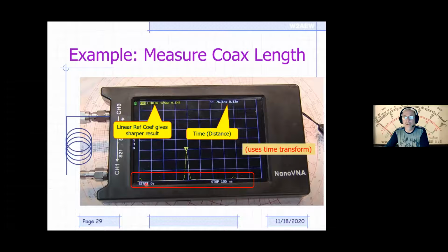So 76 nanoseconds down. Now you say, well, how far is that down my coax? It's actually the round trip delay out to the end of the coax and back. But you can tell the VNA what the velocity factor of your coax is, and it will then compute the distance for you. So in this case, it tells me that the length of that coax was 9.13 meters, or a little over 20 some odd feet of coax that I'd connected up to here.